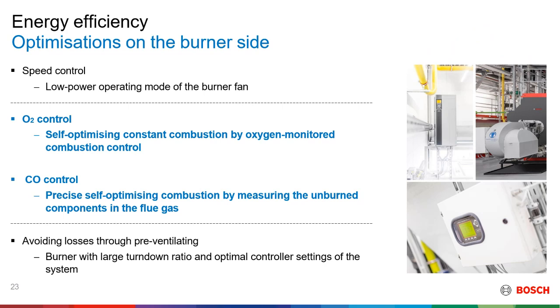Then the second point is CO control, or carbon monoxide control. This will also regulate the amount of oxygen that you are providing into the combustion process. And ideally, for complete combustion, you're not supposed to have any CO in the flue gas. If you have both O2 and CO control in your burner, it will be able to monitor the conditions of the flue gas, and in most burners, it will be able to correct the burner curves, therefore having a more efficient combustion process.